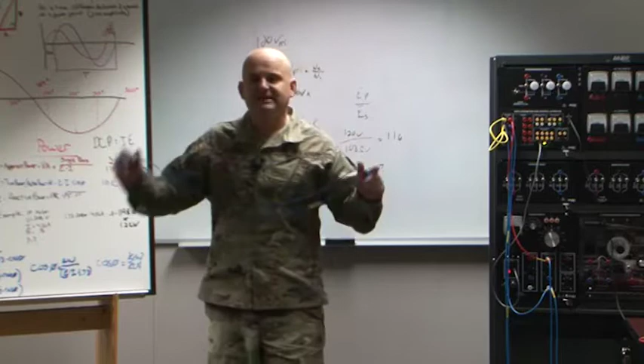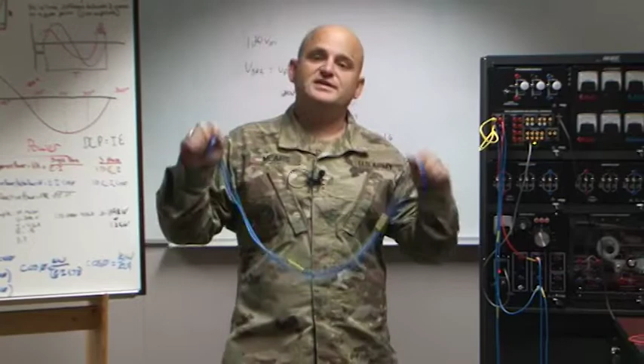However, our box, the panel that cable is all coming to, needs to be able to meet the capacity if we keep adding. These effects have second and third order effects you have to work backwards through. By increasing the conductor size, we're increasing the current carrying capability of our system, and by putting these in parallel, we're increasing the capability of our system.